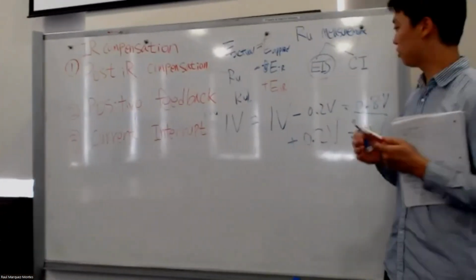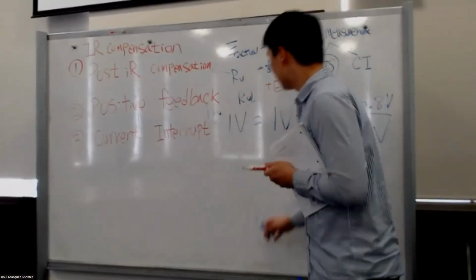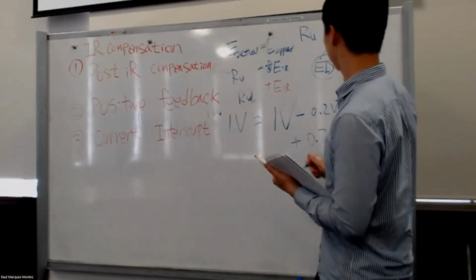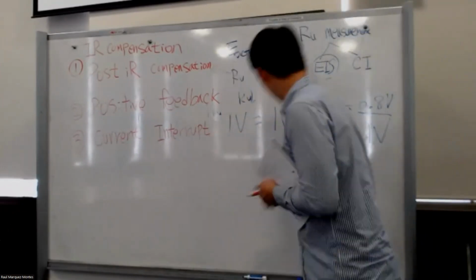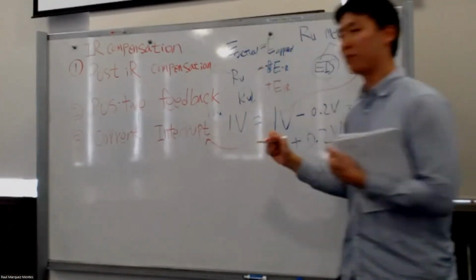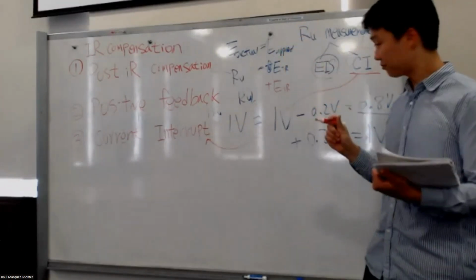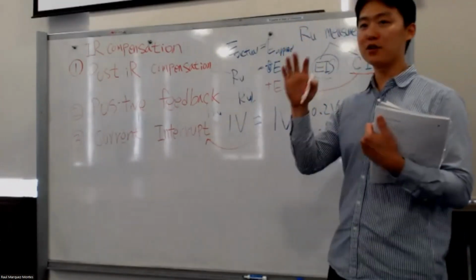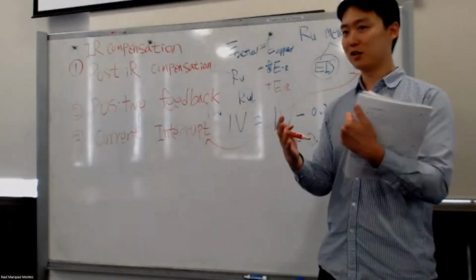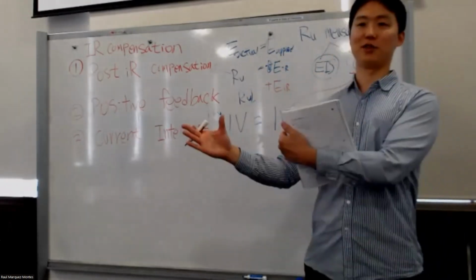And the third one, current interruption method, has a benefit over these top two methods, because this one is basically coming from this current interruption RU measurement technique. Remember, we measured the RU value using the current interruption. And as I said, they measured the RU value in 10 microseconds or 1 millisecond. So they can keep measuring the RU value during the cyclic voltammetry.